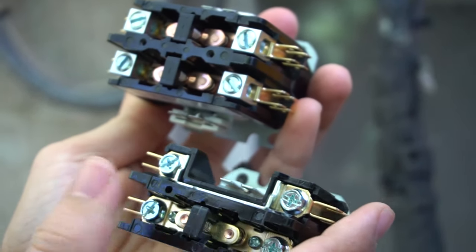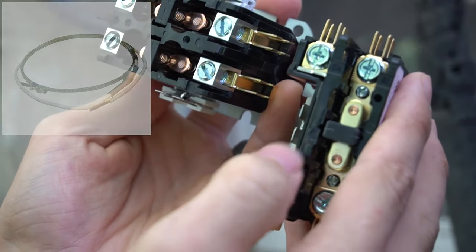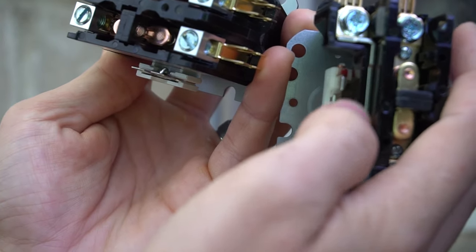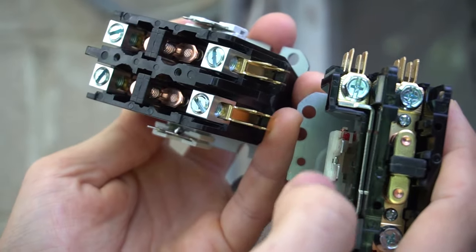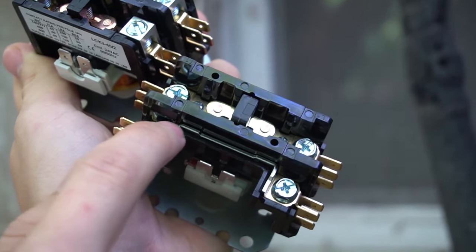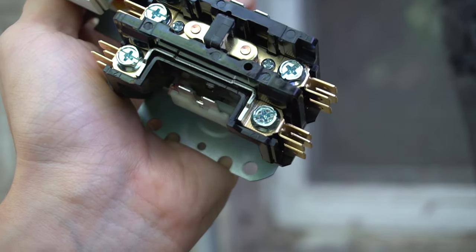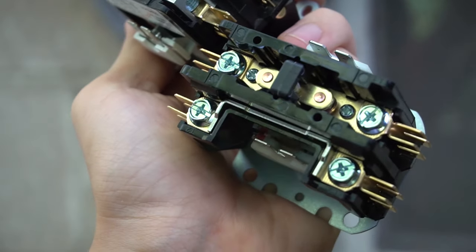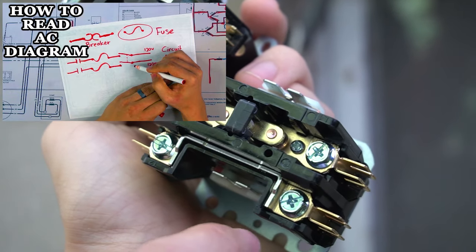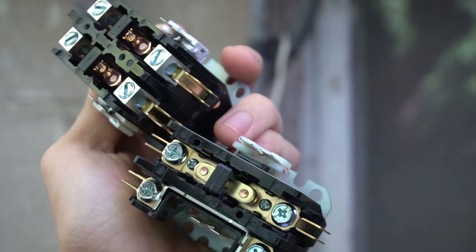It doesn't matter which contactor you get — single or double pole — with one exception: if you have a crankcase heater on your compressor. To check, open the top of your unit and look at the compressor near the bottom. If it has a crankcase heater, you definitely want a double pole contactor. The double pole has one break — when the plunger is up there's no power through it. The single pole has a straight bar, meaning you always have 120 volts sitting there, and that's what the crankcase heater needs to operate.